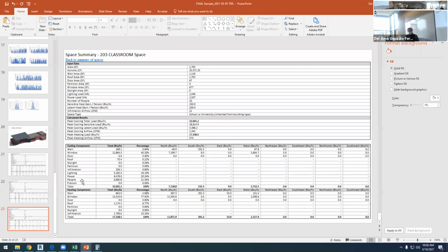So those are the internal heat gains. We have internal heat gains when it comes to calculating the cooling component. We don't consider internal heat gains when we are calculating the heating component, because we are on the safe side. This is something that makes us spend more cooling energy, but we are not considering this when we are calculating the peak cooling or heating. So those are the internal heat gains, here only in cooling.